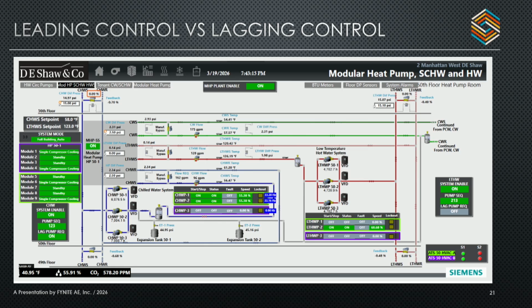So what we have decided to do is reprogram the entire control logic so that we're leading the control strategy based on flow and delta P versus chasing it with a leaving water temperature. We're going to look at how much chilled water GPM we need and stage on that many chillers, and then leave it up to the manufacturer to control the leaving water temperature beyond that point once we're in a stable pressure and flow range.